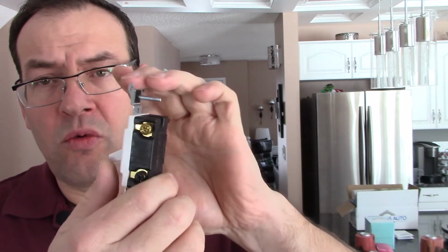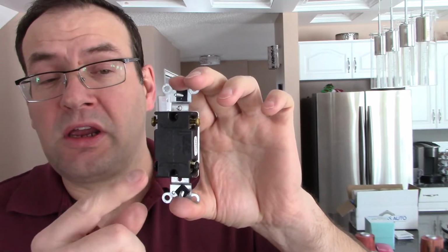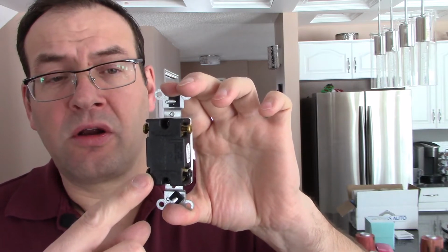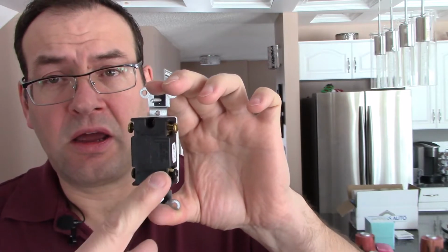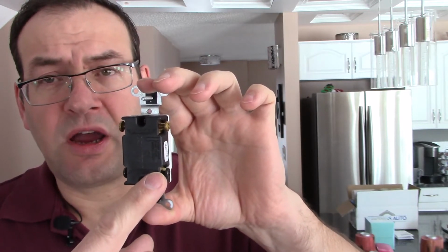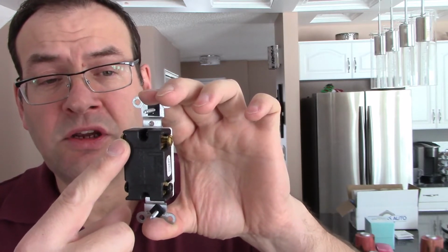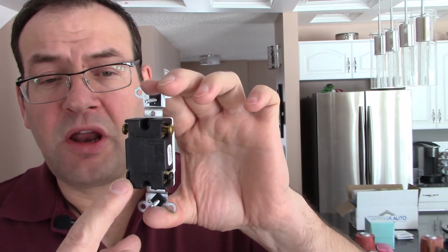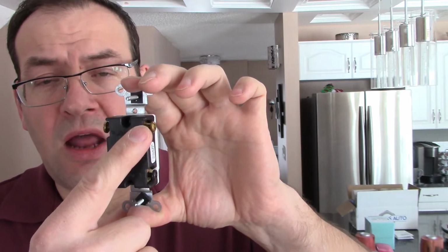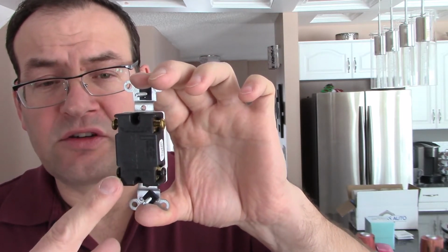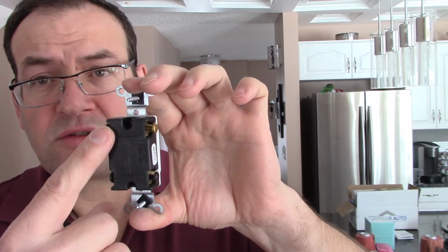Then, when you move the switch up, magically it'll connect this dark screw here across the switch to the brass screw kitty corner, and likewise the dark screw on this side across the switch to the brass screw kitty corner to that. So in one position it connects this screw to this screw and this one to this one, and in the opposite position it's an X. It connects this screw to that screw and this screw to that screw.